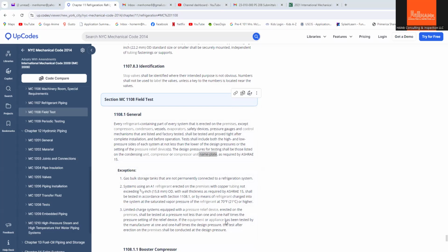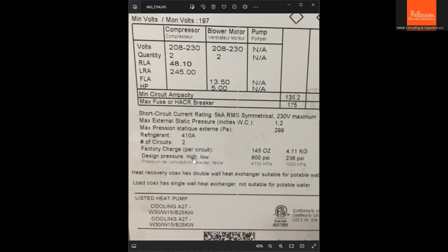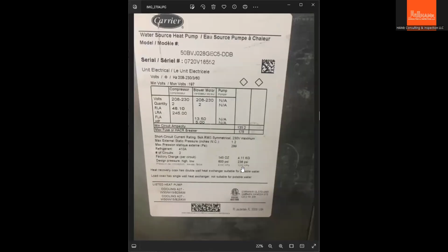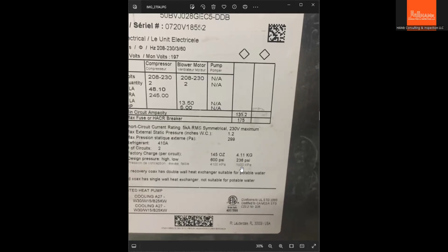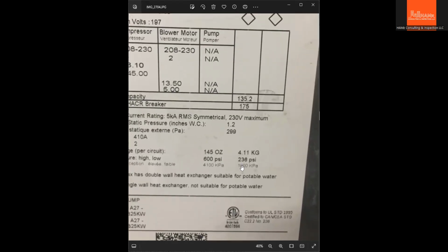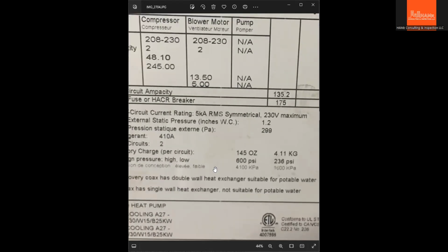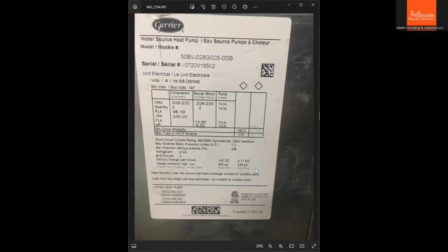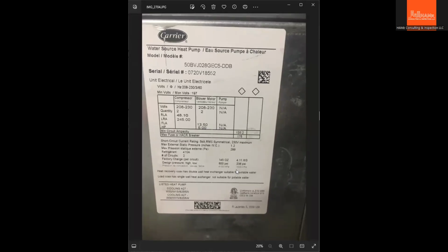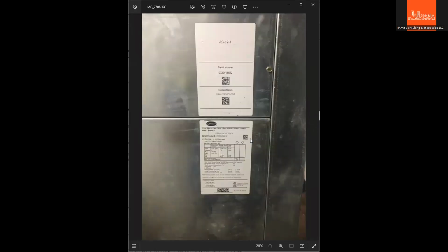In this case, this is the nameplate, and this is the design pressure, low side and high side. High side is 600 psi, low side is 236 psi. So I believe we tested it to 240, the second test, after the first test failed. So we pumped it up. We observed it for 2 hours at 240 psi, so it's not lower than the low side design pressure of the condensing unit. So we are in conformance with the code, and the system is leak free, no pressure drop, and no visible leaks on the piping connections. So that's one test. That's for chill water. And let me share some for refrigerant also.